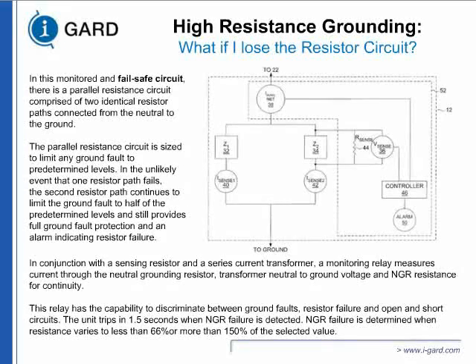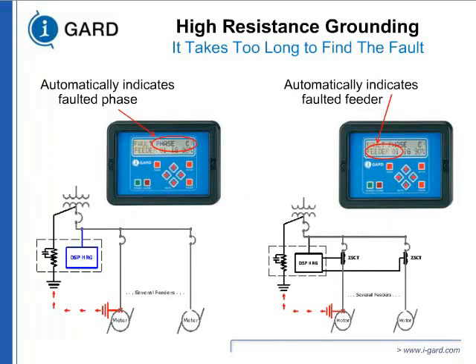Next is, it takes too long to find the fault. I cannot do like that. I don't have time to take a pulsing detector and go along the cable or somewhere and find equipment. Of course, industry obviously responded with relays with zero sequence CTs, which will automatically detect which phase has faulted, which feeder has faulted. Now, depending on your hardware, if your feeder has multiple MCCs, you may still have to go and see which MCC, motor control center, may be faulted, but at least you know which feeder it is.